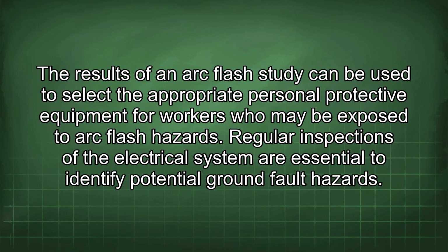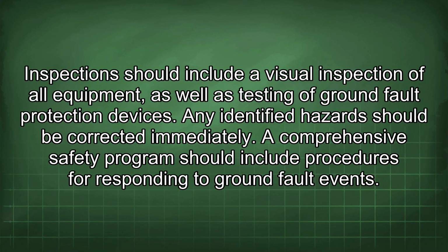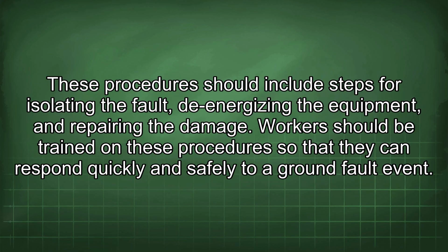Regular inspections of the electrical system are essential to identify potential ground fault hazards. Inspections should include a visual inspection of all equipment, as well as testing of ground fault protection devices. Any identified hazards should be corrected immediately. A comprehensive safety program should include procedures for responding to ground fault events. These procedures should include steps for isolating the fault, de-energizing the equipment, and repairing the damage. Workers should be trained on these procedures so that they can respond quickly and safely to a ground fault event.